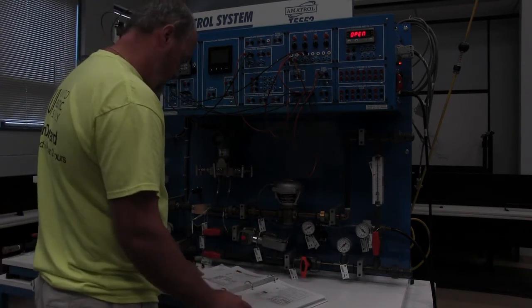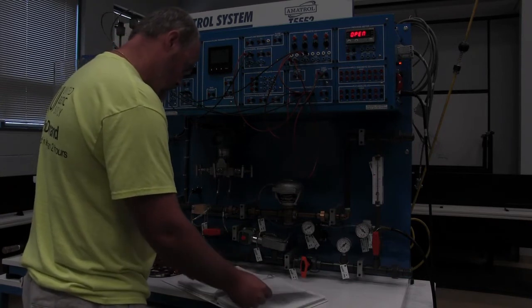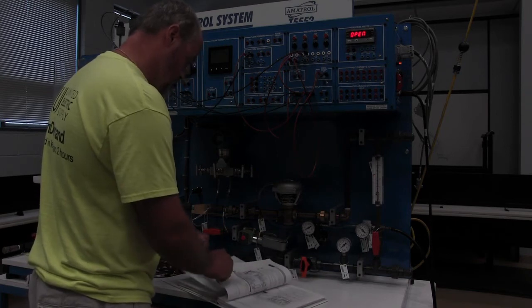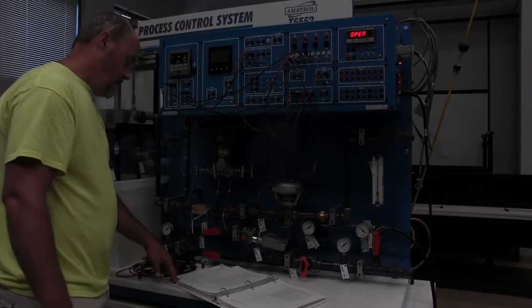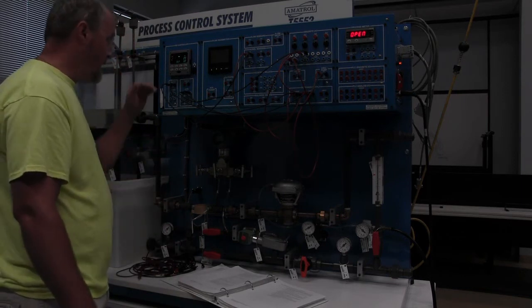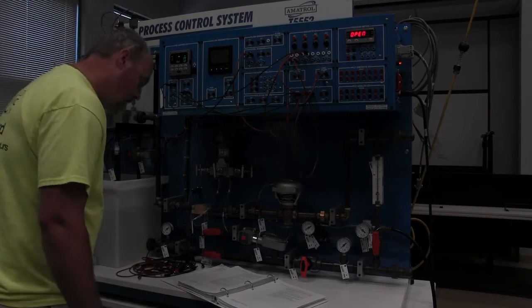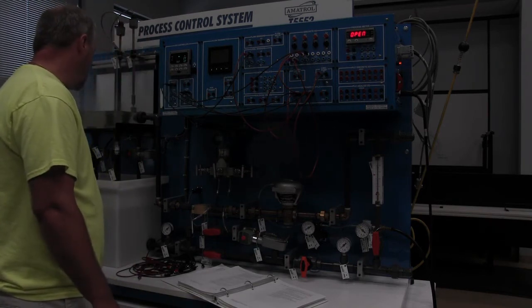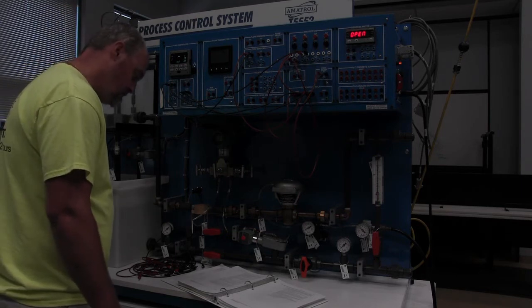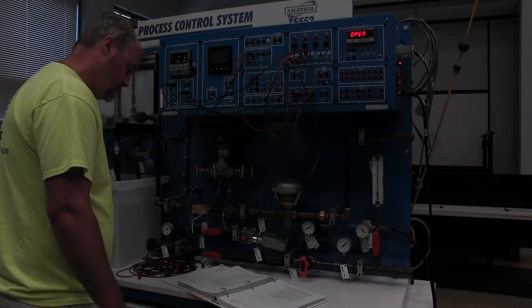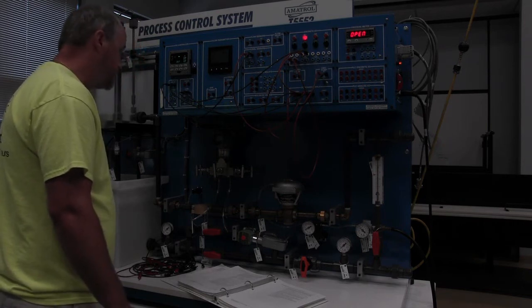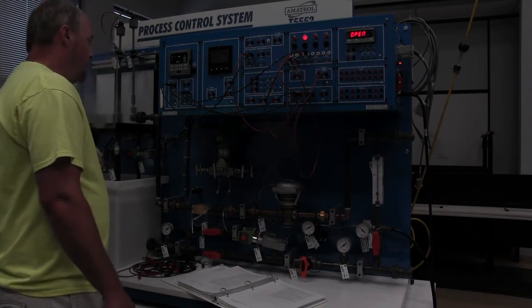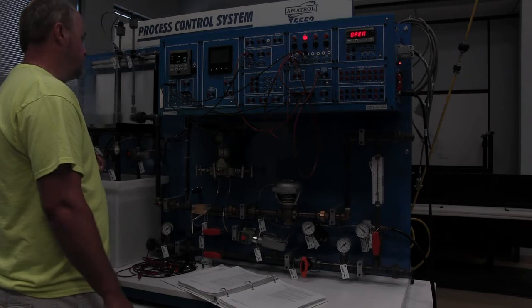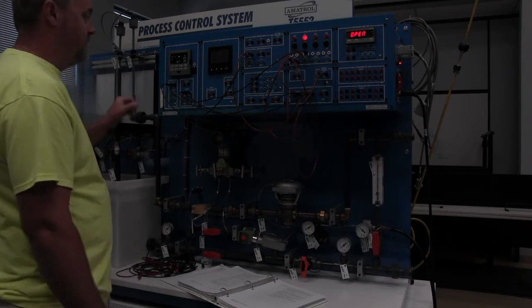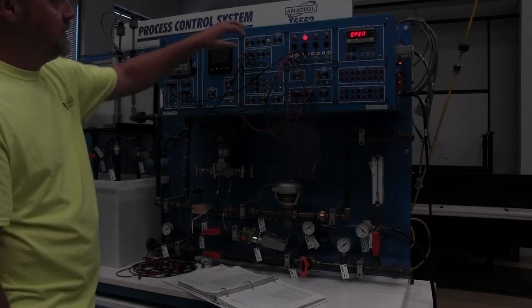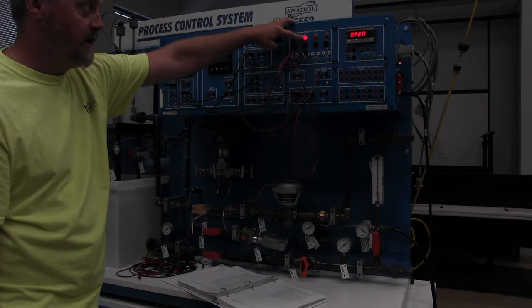All right, so now that we're... flipped one too many there. There we go. Hit the lower display key. So now we're out. And we need to drain this down. So we're back to a 0. Now that we're drained down and we're at a 0, we are less than a 1, which was our low set point, so we have an alarm. We're currently in a low alarm state right now.